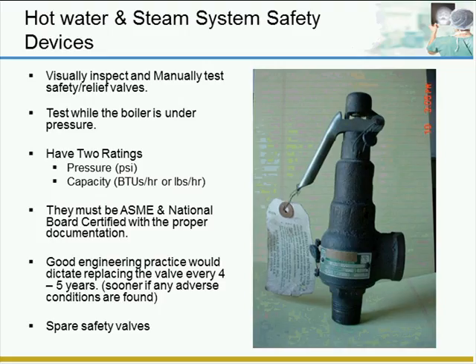Safety valve testing must be completed when the boiler is at a pressure of 75% of the rated setting on the safety valve. High-pressure boiler safety valves are fully open or fully closed. They're called pop-type safeties. You pull the trip lever to the fully open position, and the safety should fully open, and then once the pressure drops, it should fully close. If the steam leaks by, you know you have a faulty safety valve, and the safety valve should be replaced.